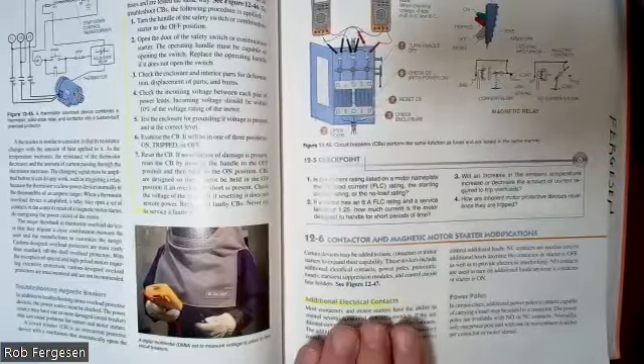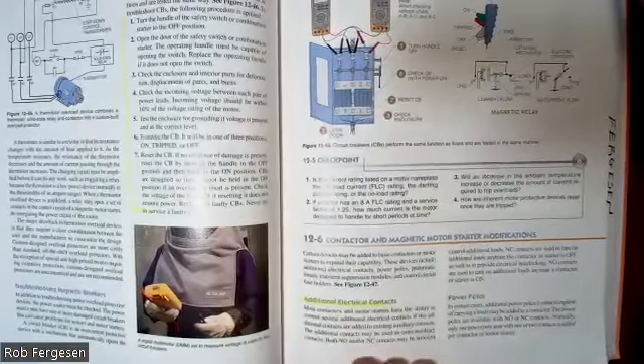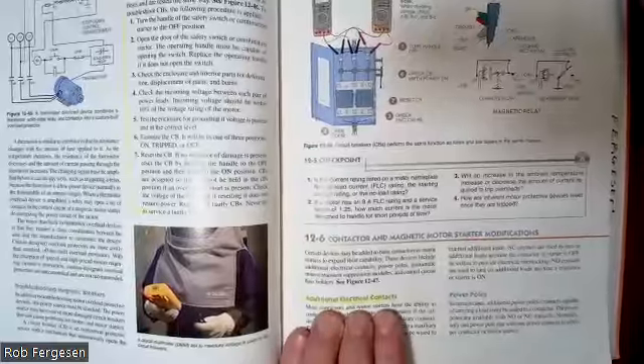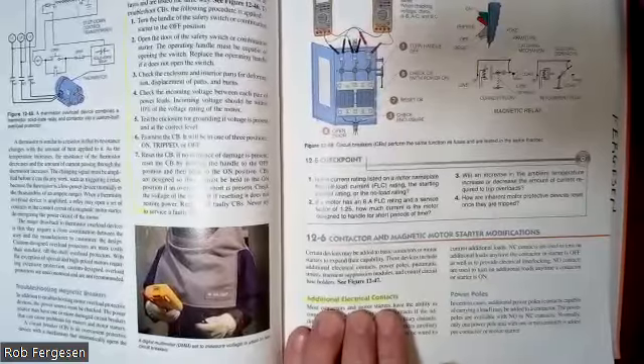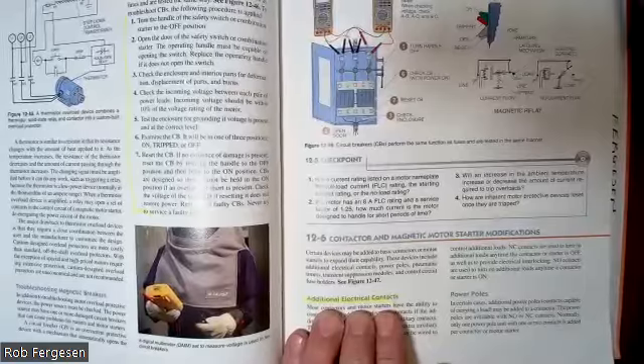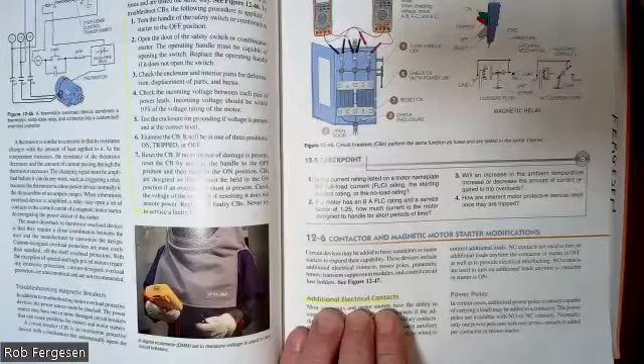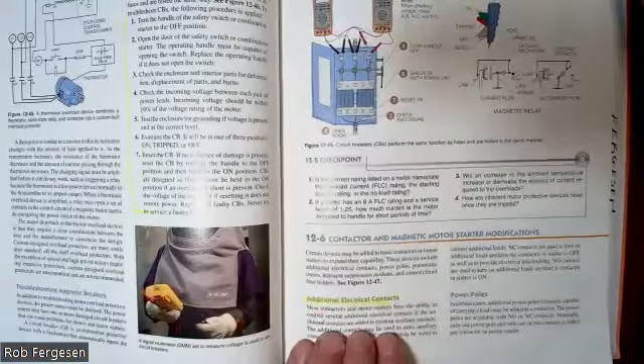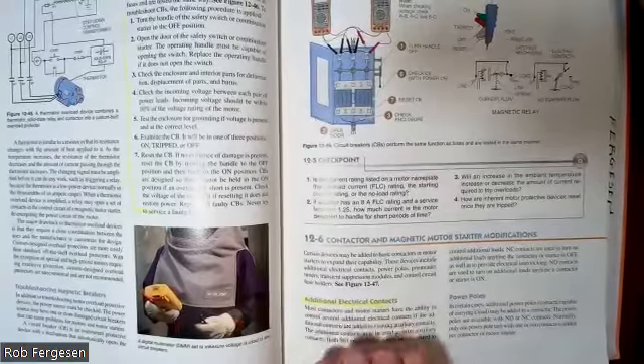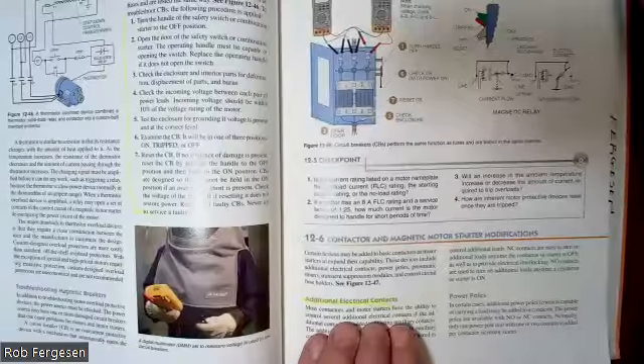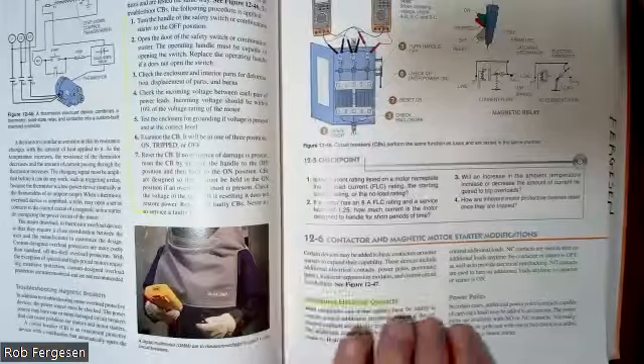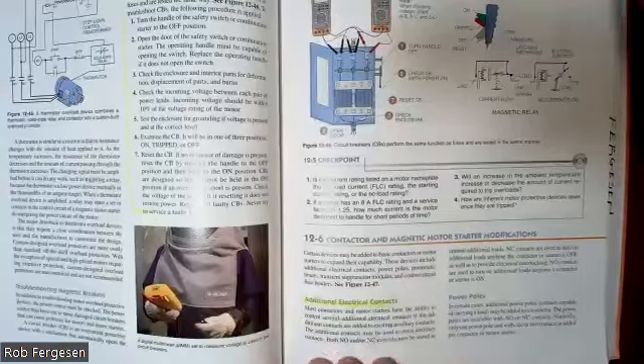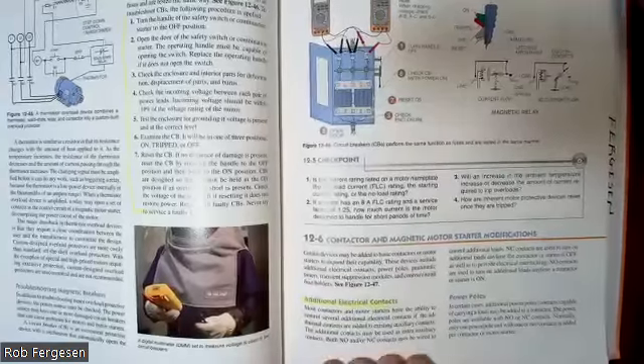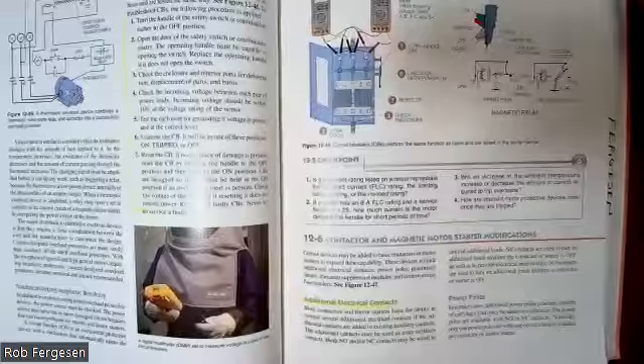But you might have more complicated circuits, and we're going to get into that in this course, where you need more than just one auxiliary contact, one extra contact. When the motor starter closes, you might want to have two extra contacts, or even an extra contact that's normally closed, so it's closed when the motor's not running and opens up when the motor runs. And you could use those for a variety of purposes that we actually are going to see in this course for some of the more advanced labs.